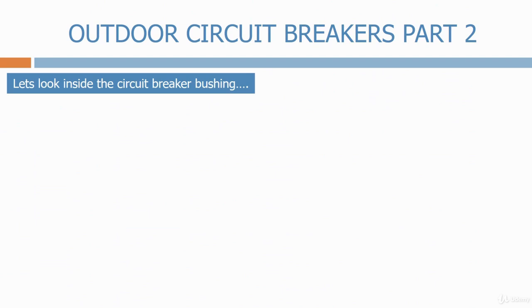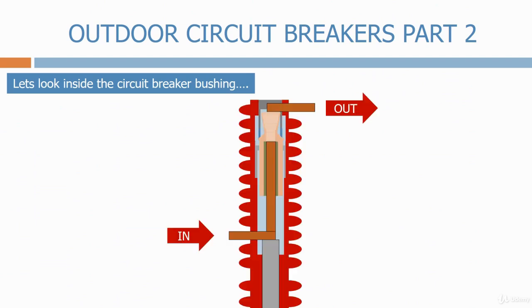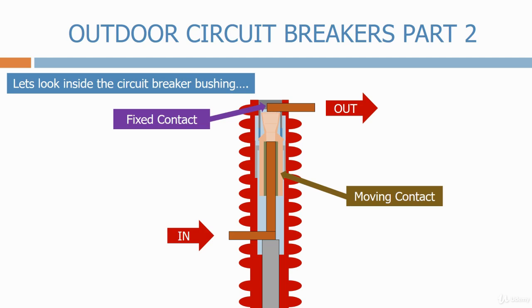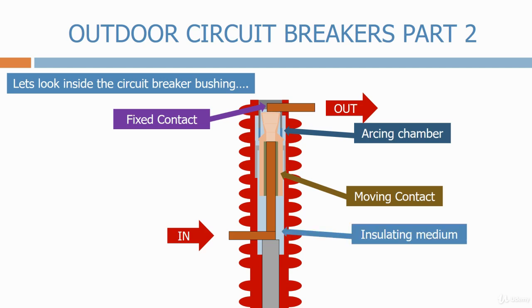Let's look inside the circuit breaker bushing. At the top of the bushing, we have the fixed contact. Below, we have the moving contact, all housed inside the arcing chamber. The arcing chamber will be filled with the insulated medium, which is normally SF6 gas for most high voltage circuit breakers. At the moment, the circuit breaker is closed.